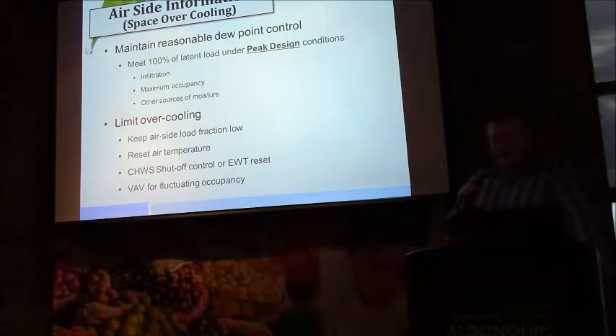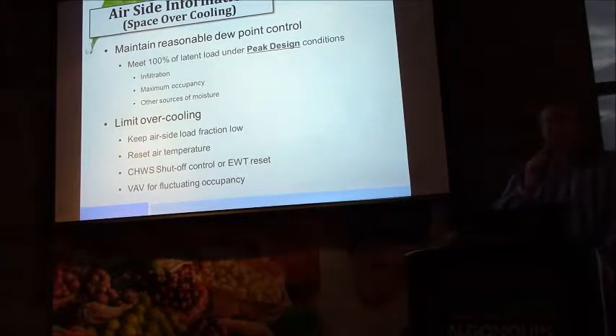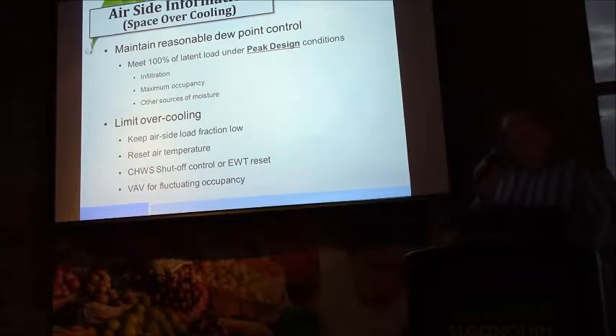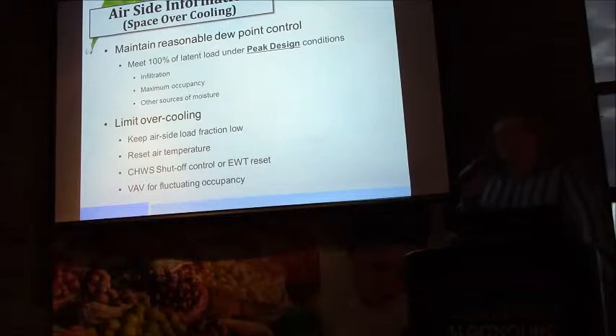And VAV for fluctuating occupancy is a bit of a misnomer. The problem with beams, again a weakness, is that the response profile of the beam itself is not linear to the pressure that's in the beam. And so ultimately what you'll find is that if we try to use a VAV box for modulating control, it effectively becomes an occupancy valve, a two-position occupancy valve, because the turndown ratio is very, very limited. You can use a VAV for modulating the flow control into the beam, but the cost effectiveness of that is generally of little benefit.